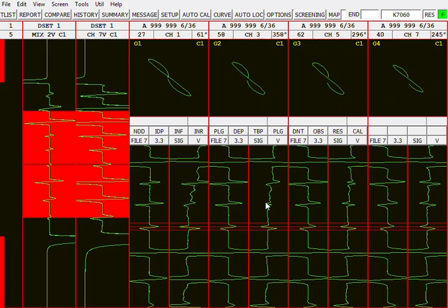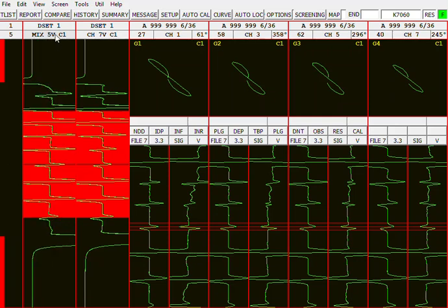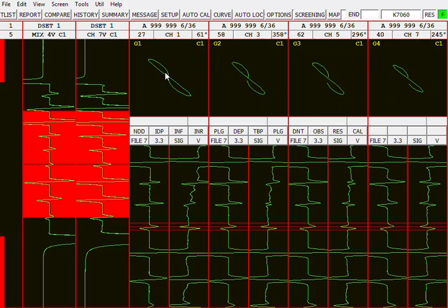All right. So you can select which strip charts you want to be in your long strip charts here. And typically you will watch vertical channels, because when you're doing data evaluation and you're looking for signals that may be indicative of flaws, they'll always have a vertical component. And if you're looking for a vertical component, you're going to watch a vertical strip chart.